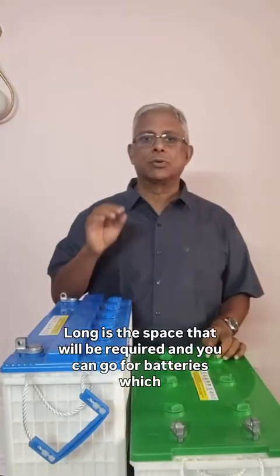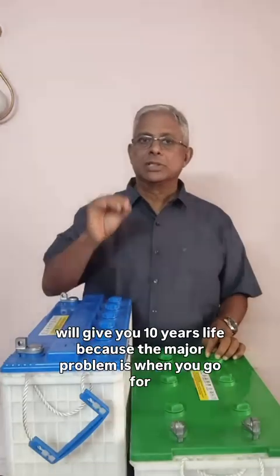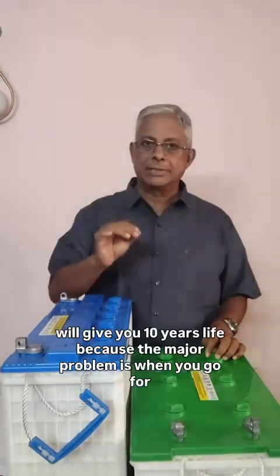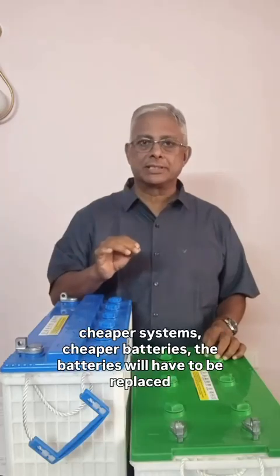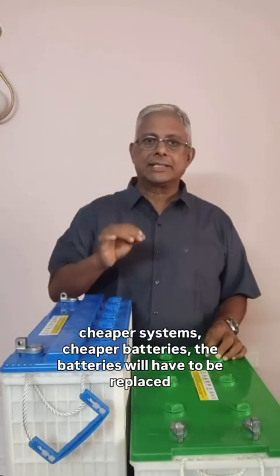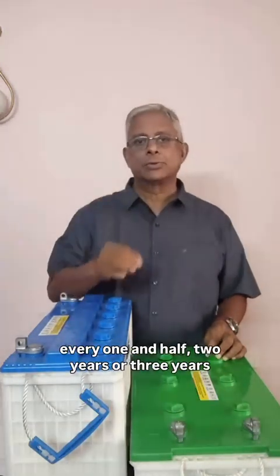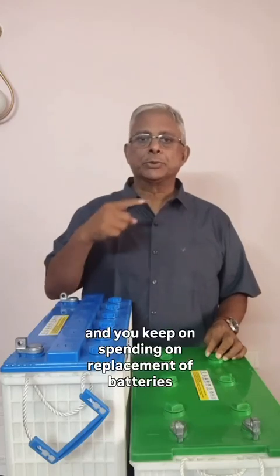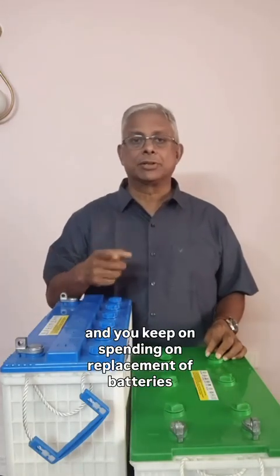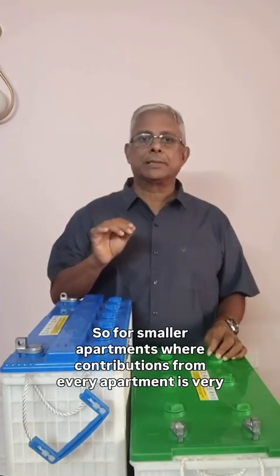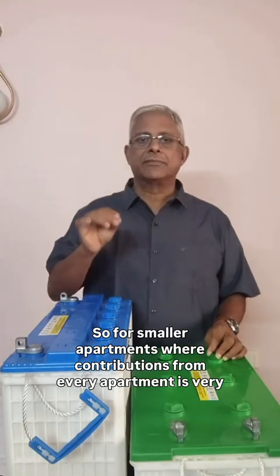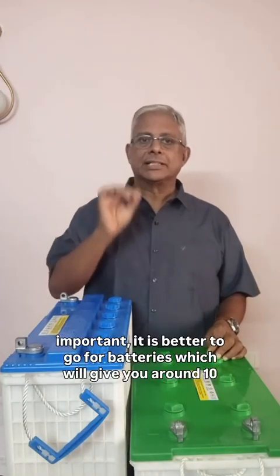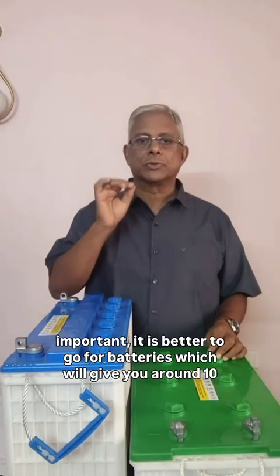You can go for batteries which will give you 10 years life. Because the major problem is when you go for cheaper systems, cheaper batteries, the batteries will have to be replaced every 1.5, 2 or 3 years, and you keep on spending on replacement of batteries. So for smaller apartments, where contributions from every apartment matter, it is better to go for batteries which will give you around 10 years life, or 1200 to 1500 cycles.